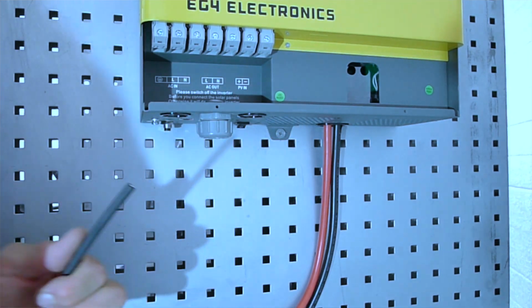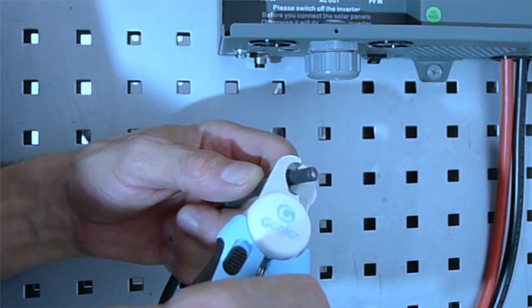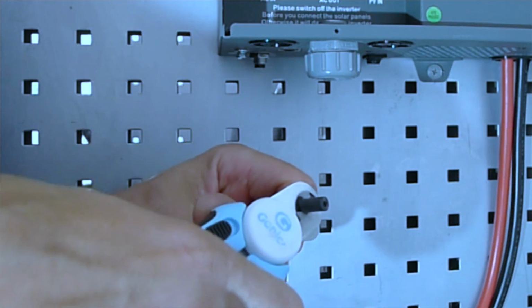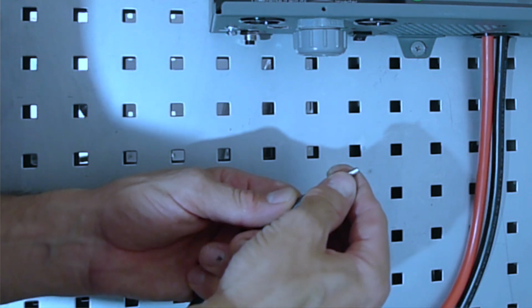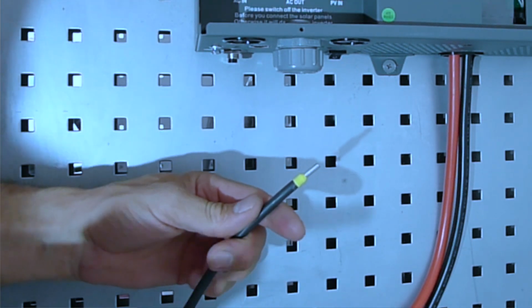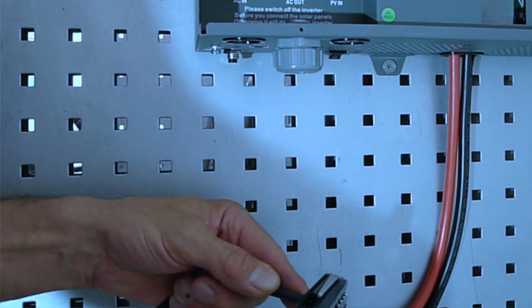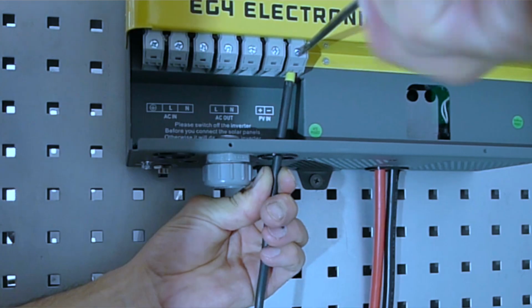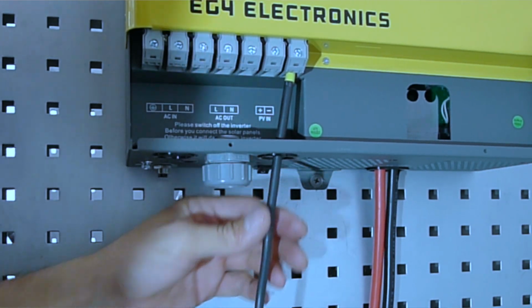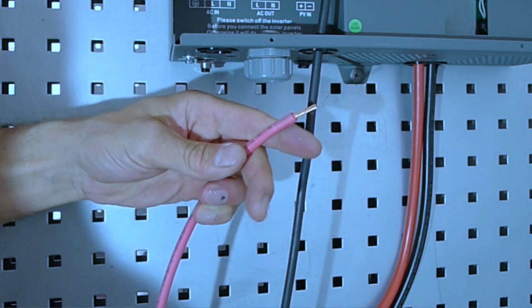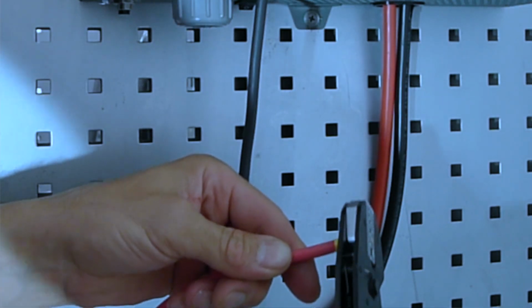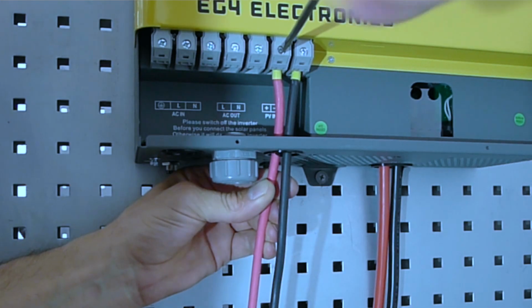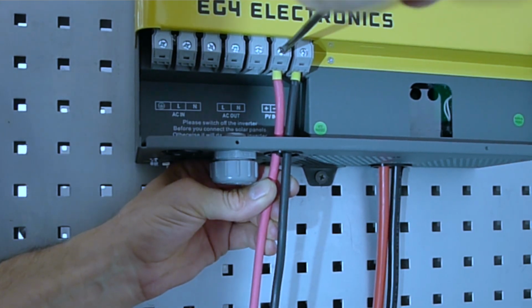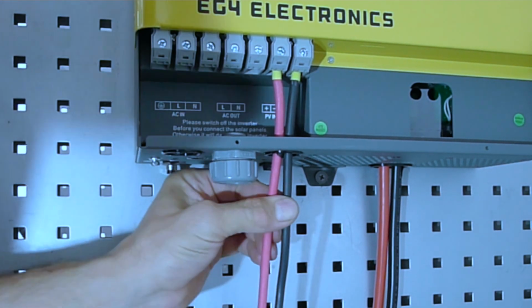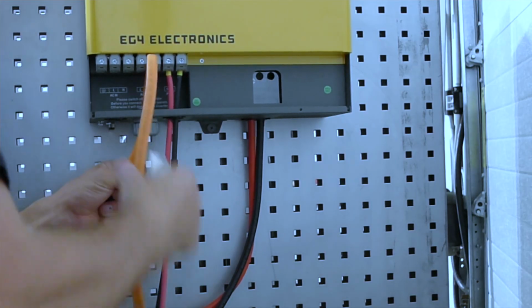Next, let's install the PV wires. Remove 10 mm or 0.4 inch of the insulation sleeve from the positive and negative conductors. For DC wires, I strongly suggest using ferrules for two reasons. First, if we secure DC wires directly with bolts, the bolt can damage the thin wires. Second, if we use the right size ferrules, that makes the wire stronger at the connection point, so it is able to handle more amps as well. Most of the time, the wire is not the failure in the system, it is the connection. The battery and PV cables are connected.